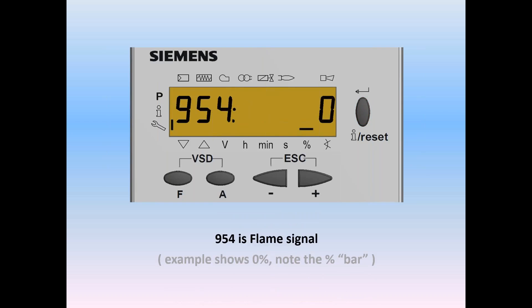The first thing you'll see on your screen is 954 flashing. Notice that on the left, the little wrench has a bar indicating we're at the service level. The parameter is 954 and the value is 0. There's also a bar above the percent sign telling us we're getting a 0% flame signal, because the burner shut down.